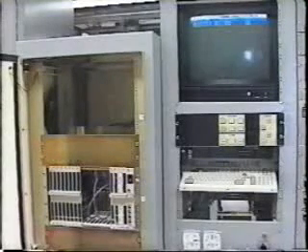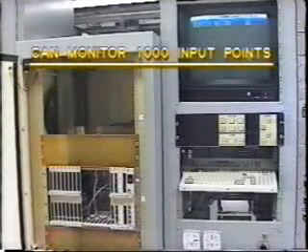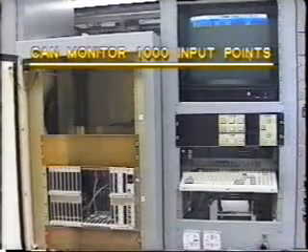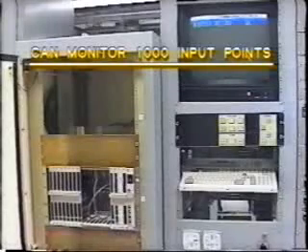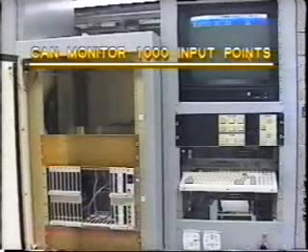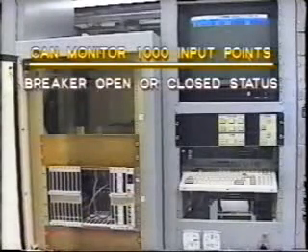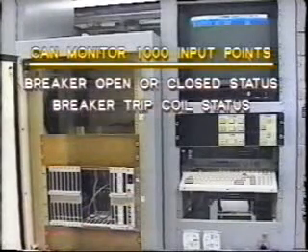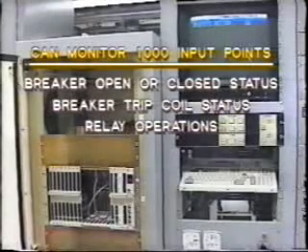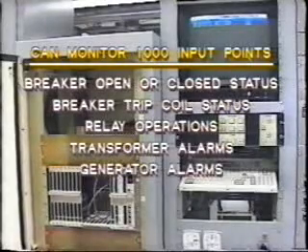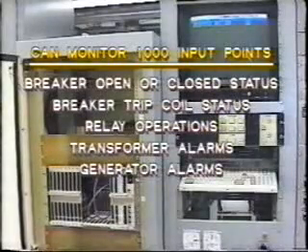The SER may be an integral part of the oscillograph system, but quite often it is a stand-alone machine. This type of recorder is capable of monitoring 1,000 input points — for example, breaker open or closed status, breaker trip coil status, relay operations, transformer and generator alarms, and so on.